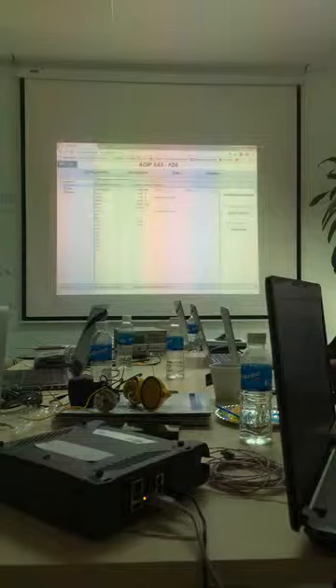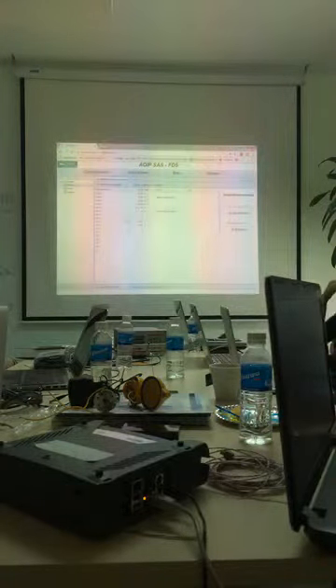So start. So you see, first probe is connected, it's functioning. Then I didn't connect anything there, so broken wire. You know that there is a trouble. Then I configured a thermocouple. It is not able to detect the fault. There, voltage signals. Voltage signals, maybe we are really at 0, so we don't detect any troubles. Calculation, broken wire, because we are linked there. Then we have the output, we have nothing. And if we go on alarms, no alarm displayed, because at the moment I didn't trigger any alarms.